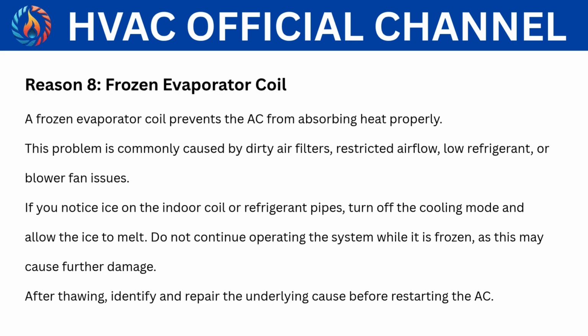Reason 8. Frozen evaporator coil. A frozen evaporator coil prevents the AC from absorbing heat properly. This problem is commonly caused by dirty air filters, restricted airflow, low refrigerant, or blower fan issues. If you notice ice on the indoor coil or refrigerant pipes, turn off the cooling mode and allow the ice to melt. Do not continue operating the system while it is frozen, as this may cause further damage. After thawing, identify and repair the underlying cause before restarting the AC.